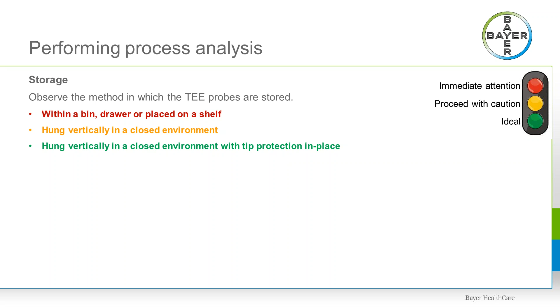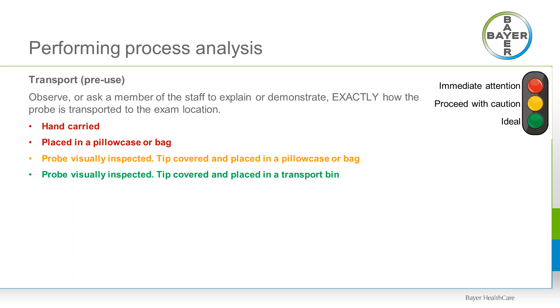All right, how's the probe transported to the exam location? Is it hand carried? Is it placed in a bag or a pillowcase? Is the probe inspected prior to use or whenever it's removed from storage? Is the transport bin used and its tip protection in place? If it's hand carried or transported in the bag, there's a definite need for improvement. Ideally, the probe should be transported within a bin with tip protection in place. It's also a good idea to visually inspect the probe prior to each use. Even if the probe is being transported within a bin or a pillowcase, employing tip protection and a visual inspection does make for an acceptable method.